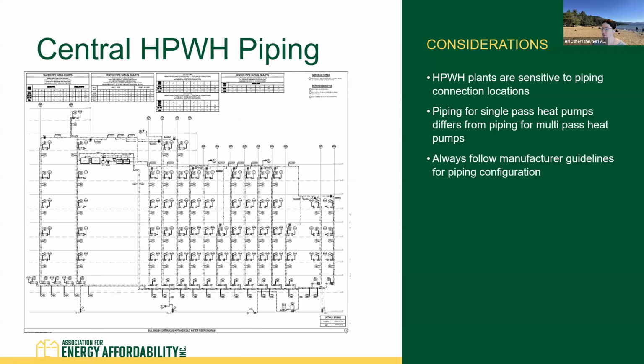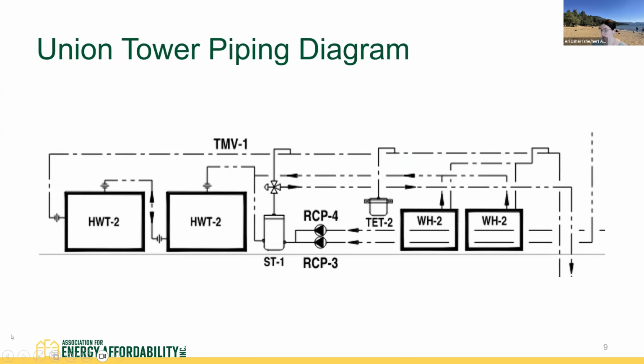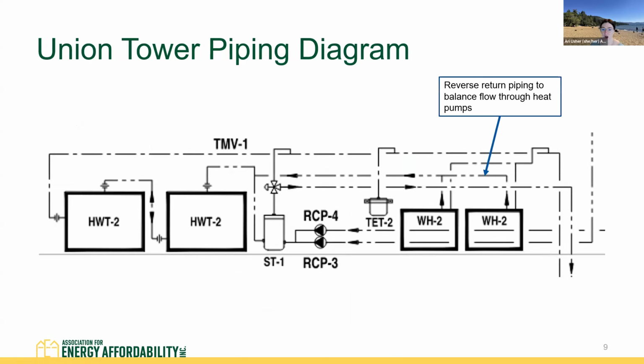Great. So let's take a look at the piping diagram for Union Tower. Okay, so central water heating plants are a bit sensitive to piping connections, so it's important to make sure that the connections are always done per the manufacturer's installation manual. But there's a couple of key concepts to remember. So reverse return piping is going to balance water flow through the heat pumps.